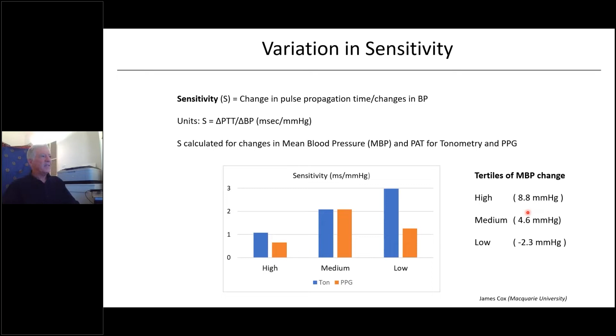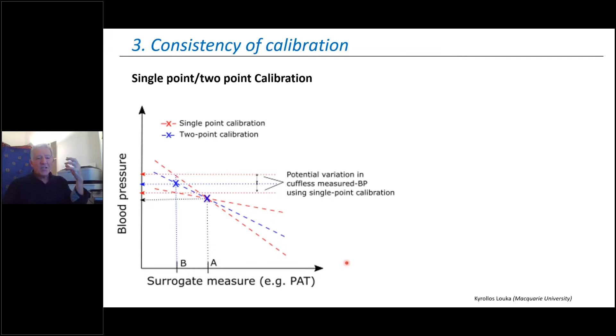Another one is looking at the consistency of calibration using a 2-point calibration. Now, a lot of these devices ask you to measure blood pressure and measure the transit time, and that's the calibration. So usually, with a single-point calibration, for example, one blood pressure measurement corresponds to one transit time measurement. If there is a change of blood pressure, what will the device do? There has to be some slope that is put in, some calibration. And so you can see, depending on what slope the device has, will determine what the next measurement of blood pressure is if it changes. Now, of course, that can be fixed if one has two measurements, so a 2-point calibration. And you can see that the same change in transit time with these different calibration points could actually achieve different values of blood pressure. That's the first point.